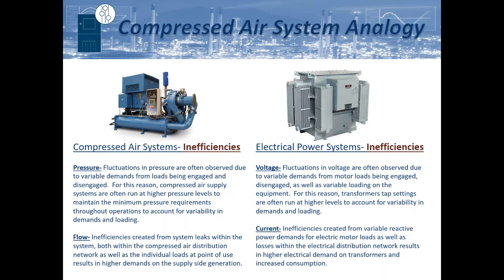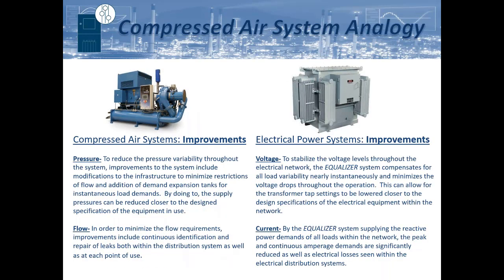As well, on a compressed air system, you have different inefficiencies, whether that be leaks or turbulence within the flow. The same holds true with current. You're going to have harmonics, which is the turbulence within the flow, and the reactive power is analogous with some of your leak loads as well. So in order to improve upon a compressed air system, oftentimes you might add a demand expansion tank in order to account for those instantaneous pressure drops and maintain a more stable pressure on the network. That's in essence what an equalizer does. It provides that instantaneous load demand response to allow for that pressure, that voltage, to be stabilized on that network.